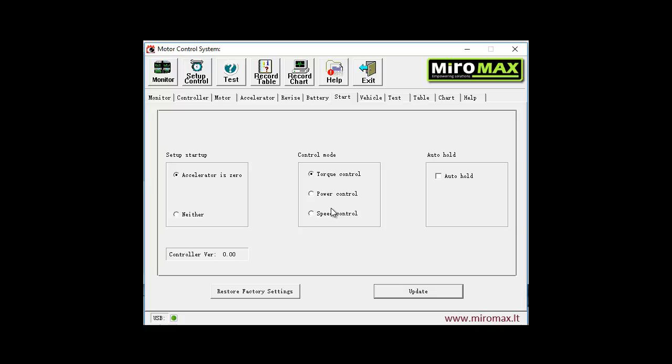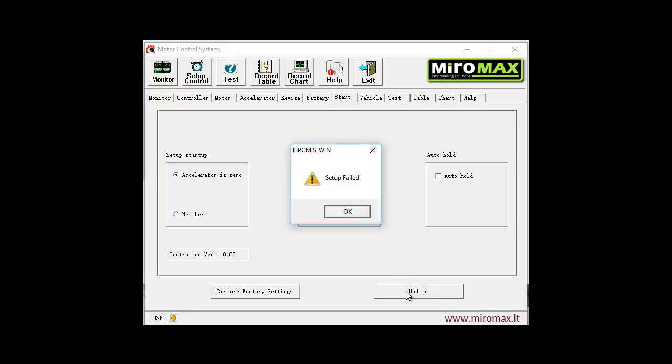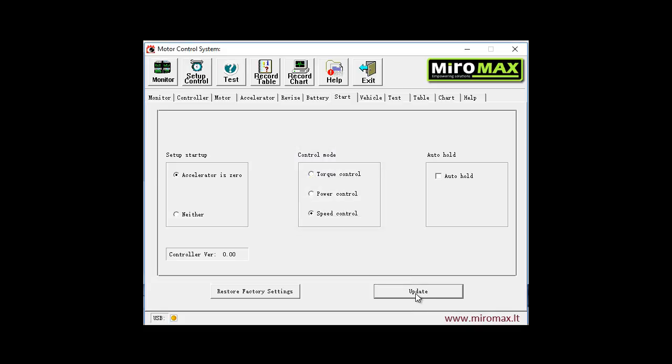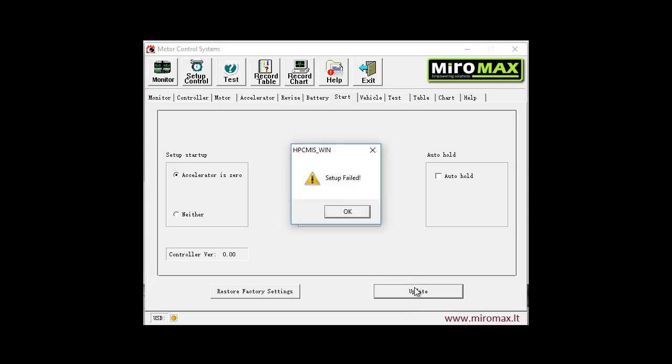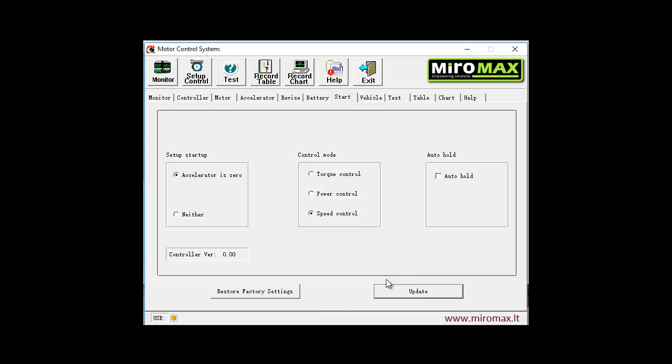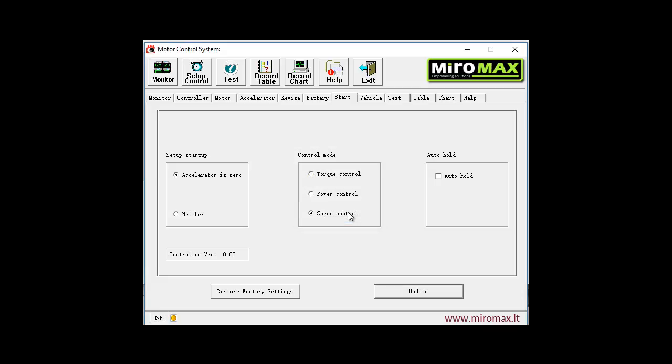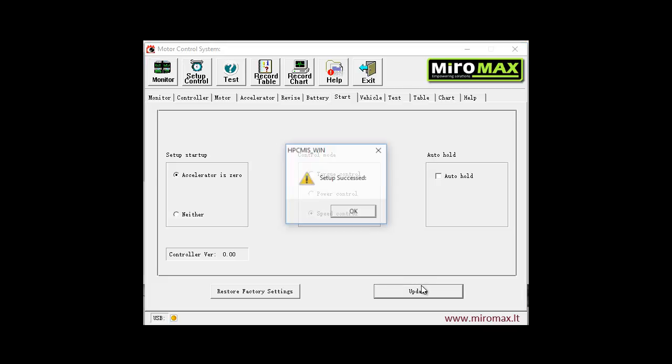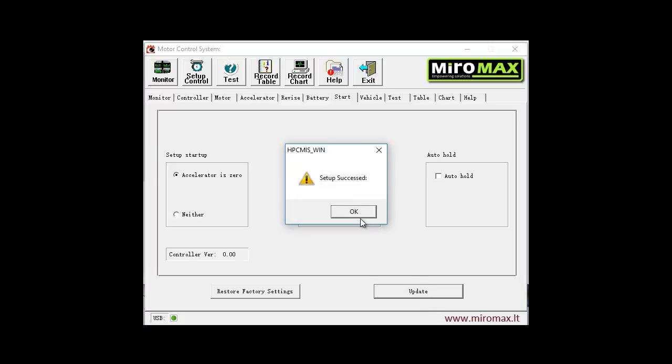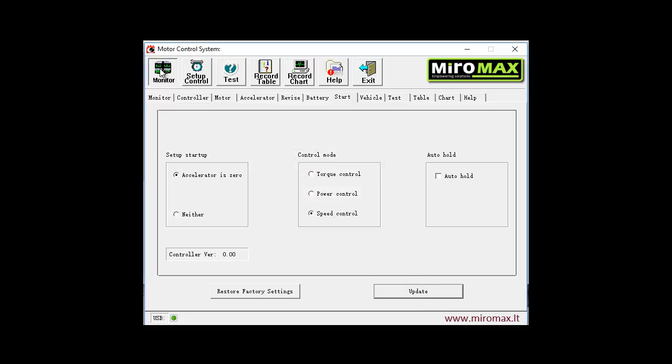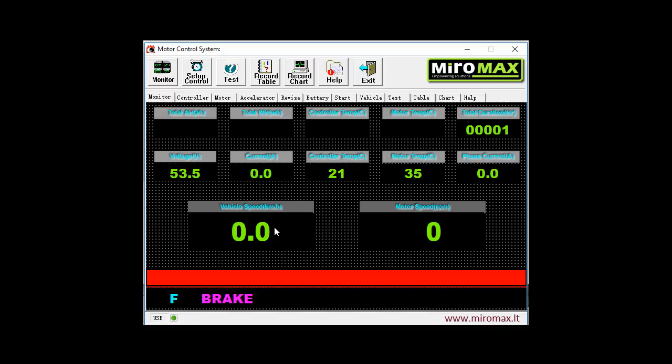The controller supply should be switched off and on, because exactly at this time the set parameters are being transferred to the controller. You may update parameters as you want, but they will be transferred to the controller just in case when power supply is switched off and then on.